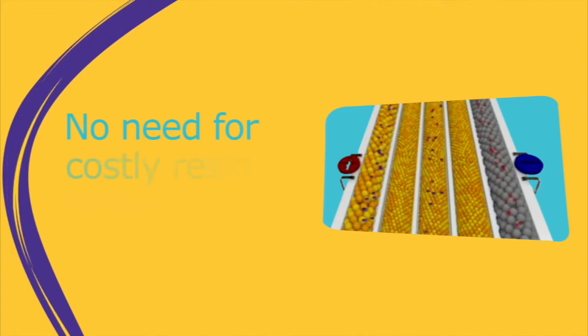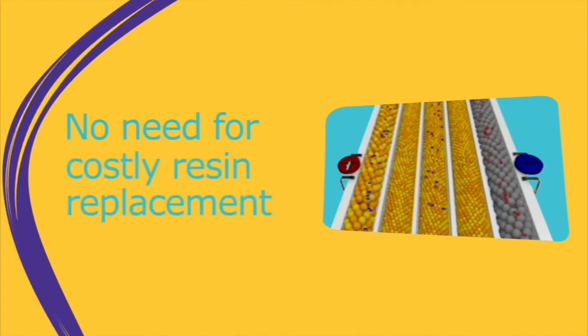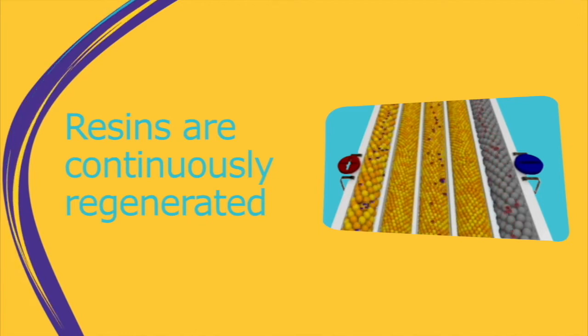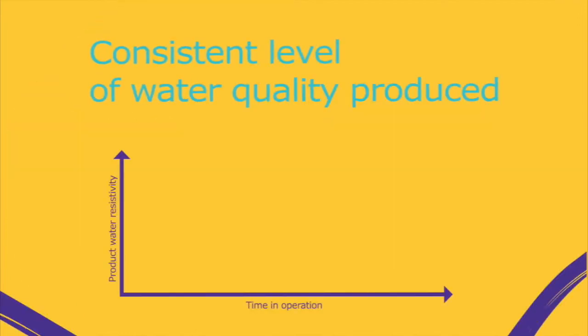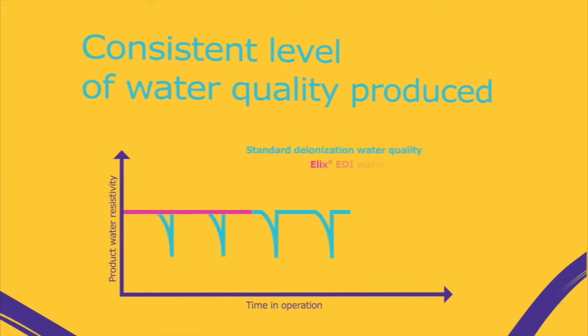Unlike resins used in service DI, there is no need for chemical regeneration or costly resin replacement. Resins are continuously regenerated inside the ELIX module, leading to a constant and consistent high level of water quality produced.